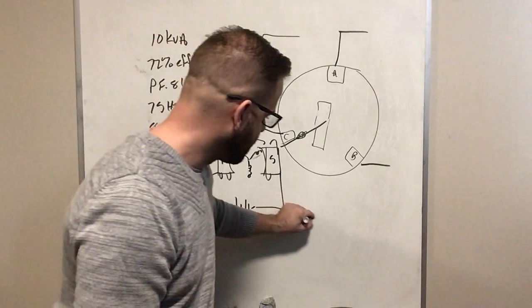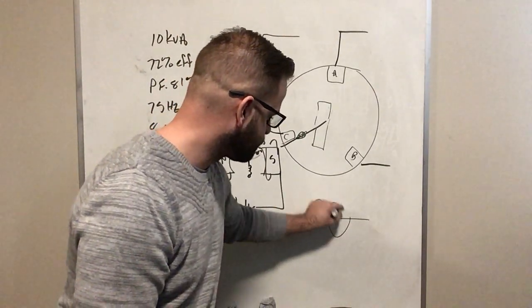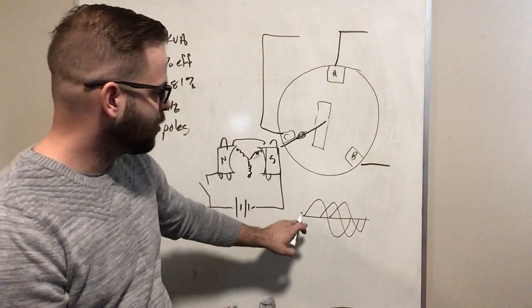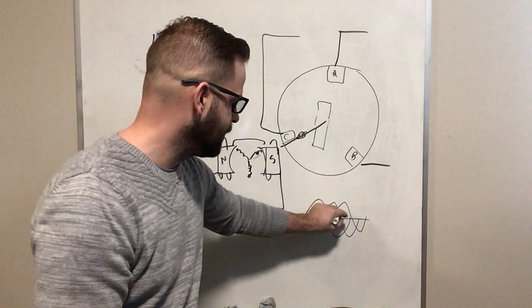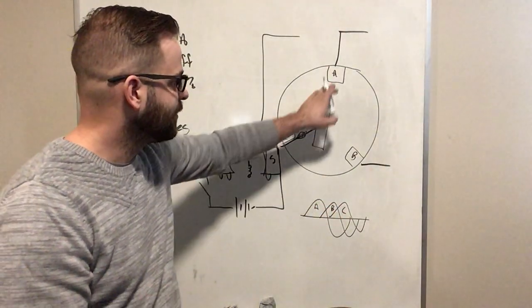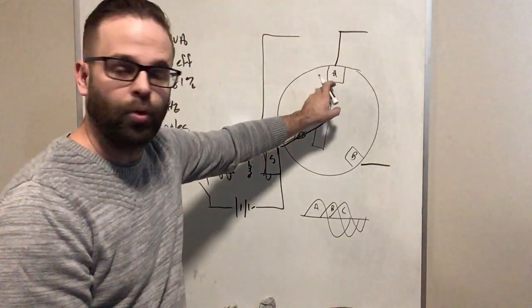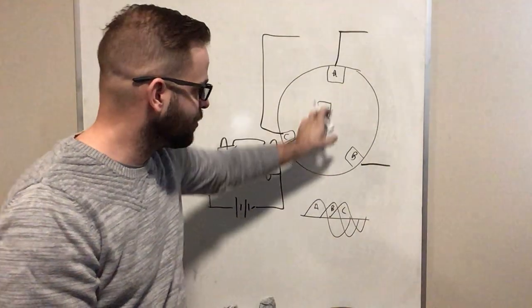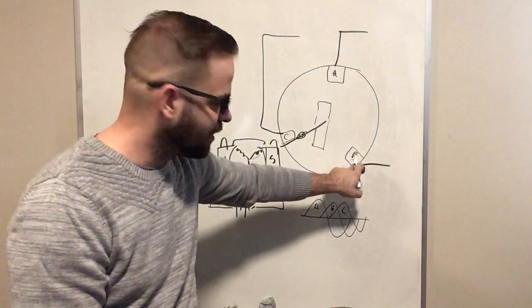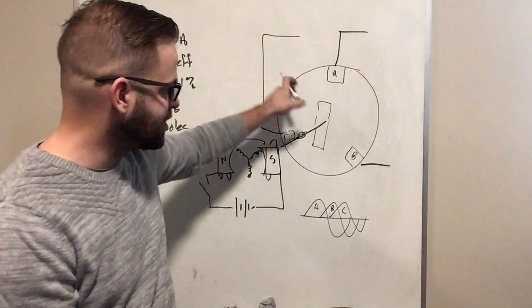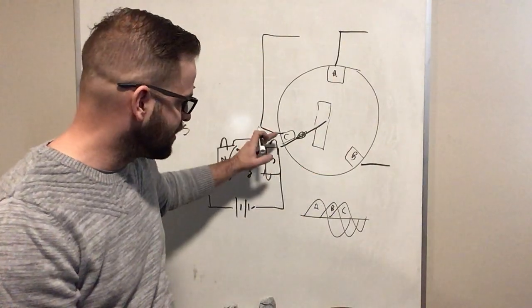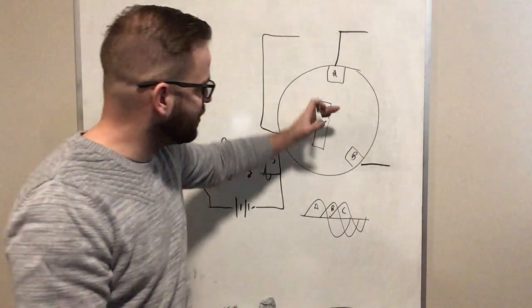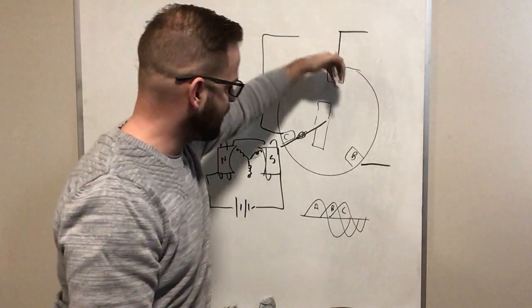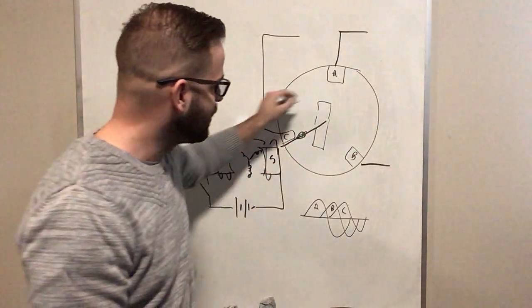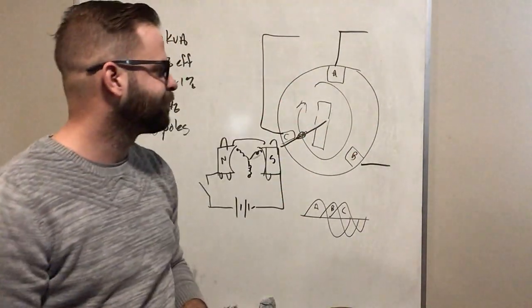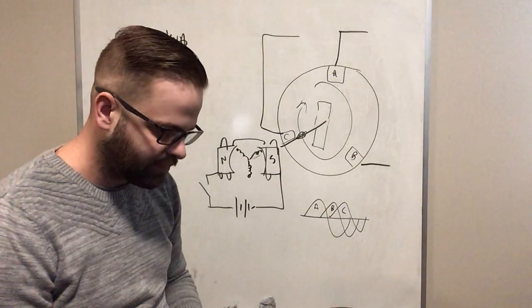If you remember, I've got a three-phase sine wave that looks like that. So this would be my A, B, C. In the first fraction of a second, that one sees a voltage. Once I see a voltage and current is flowing, a magnetic field forms, so I get a magnetic field formed this way. Then I get current on B showing up here, so my magnetic field is now here as that one's collapsing. Then as this one's collapsing, I get my phase 3 being created. So my magnetic field goes from this way to this way to this way, and I end up getting a rotating magnetic field inside the center of the motor.